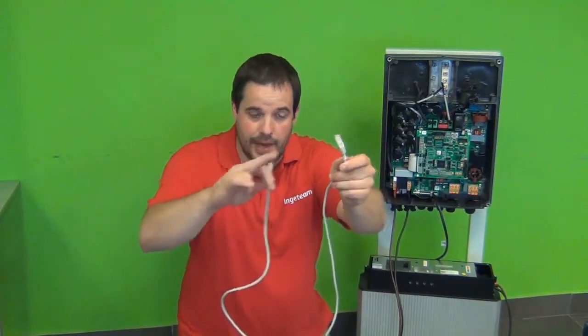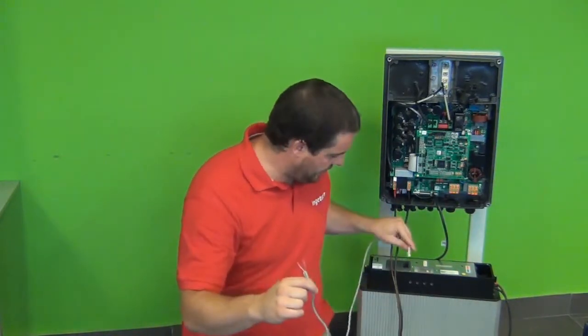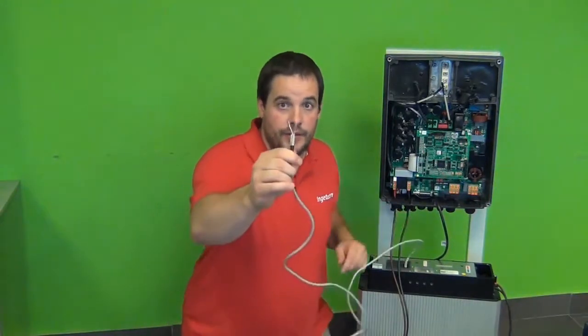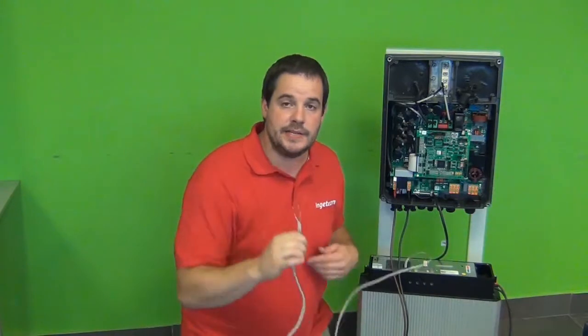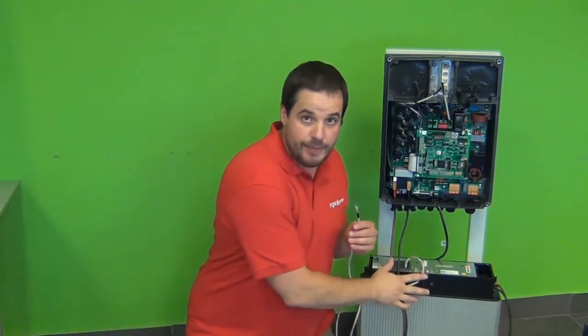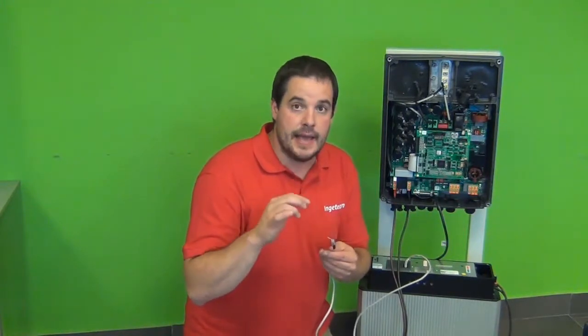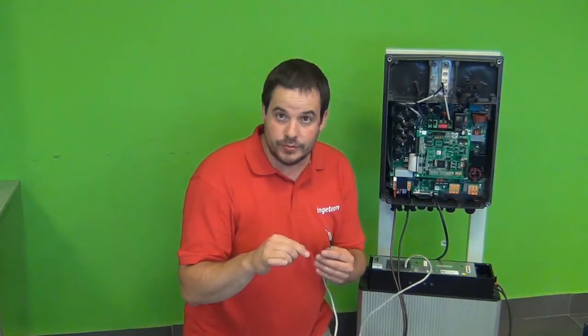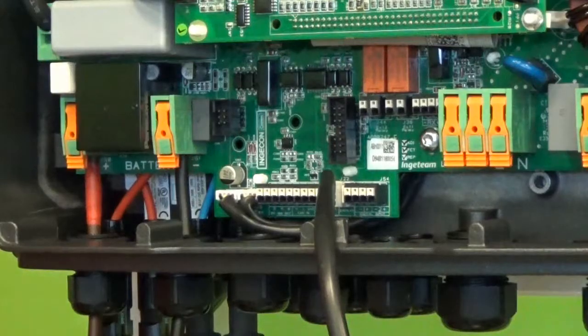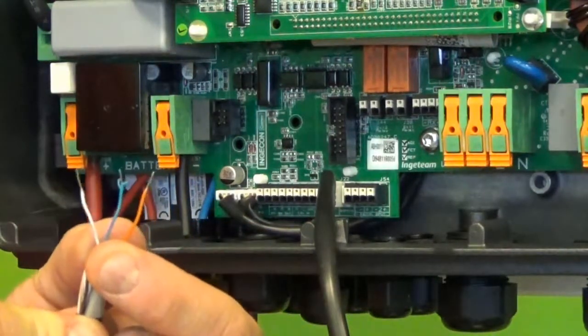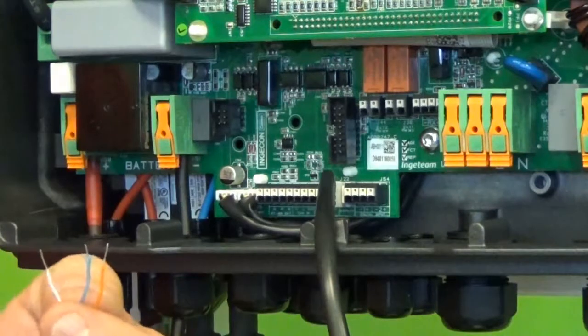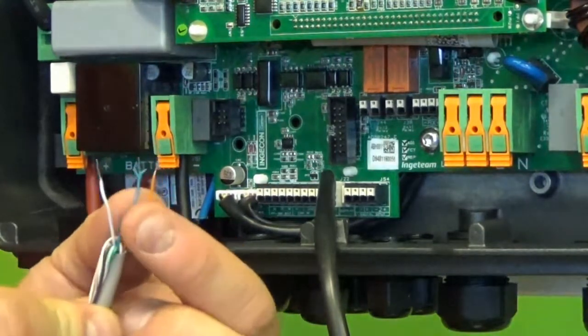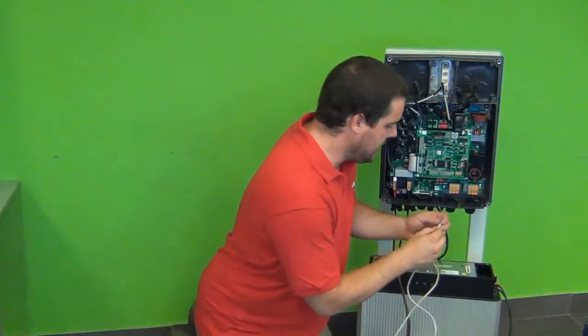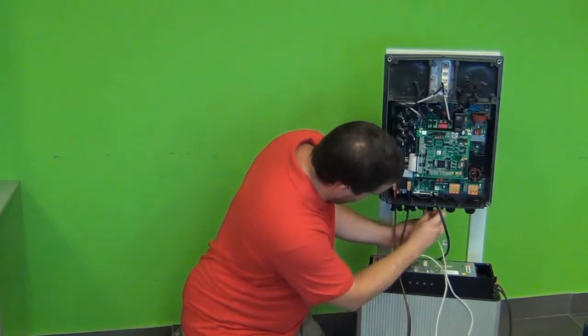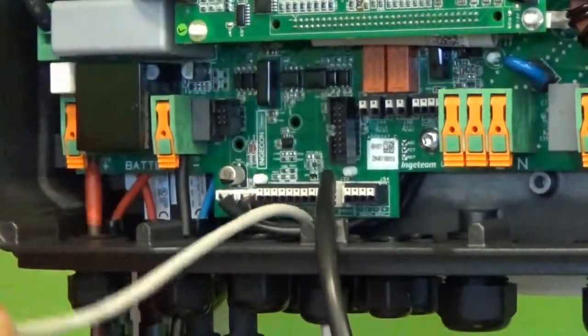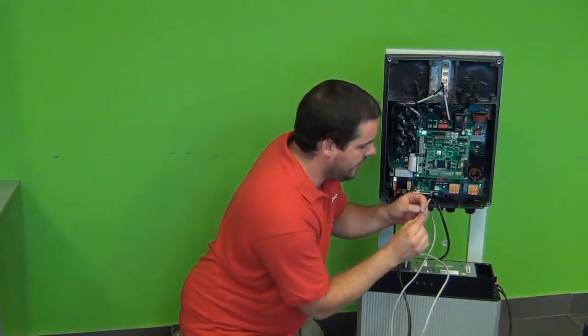On the one end of this cable, I have an RJ45 connector that is plugged over here. And on the other end, I have 3 stripped wires. What I recommend is that you go through the manual of your lithium-ion battery and you identify where is the CAN high, the CAN low, and the ground for the BMS of the batteries, all right? In this case, the blue cable will be the CAN high, the blue and white color cable will be the CAN low, and the orange will be the ground. So what I do is I put this cable through the cable gland here. I take it through the top, and now I'm going to proceed to make all the connections.